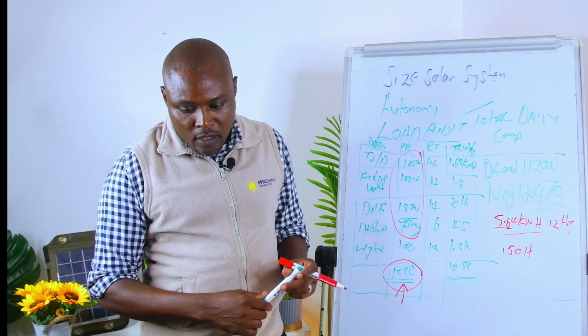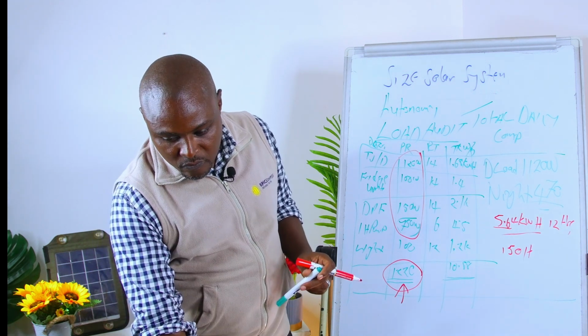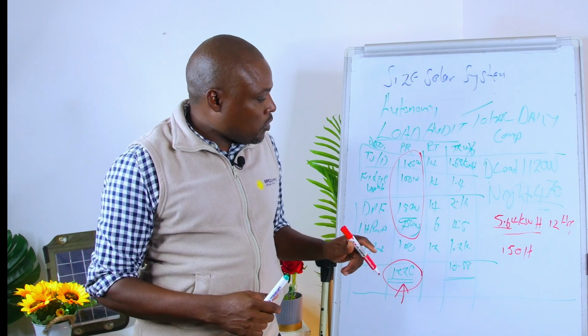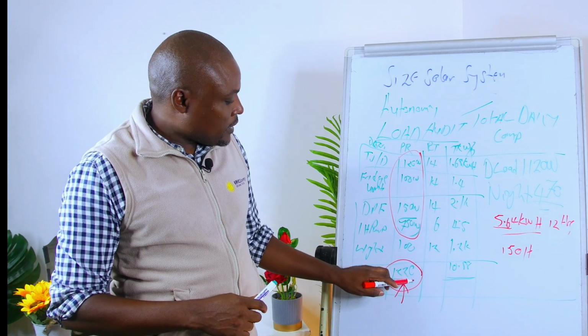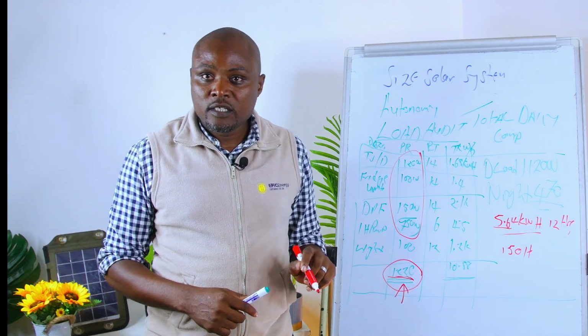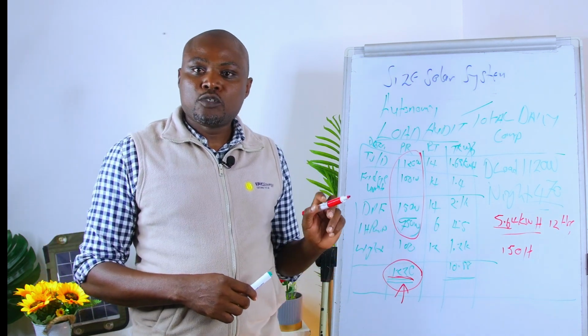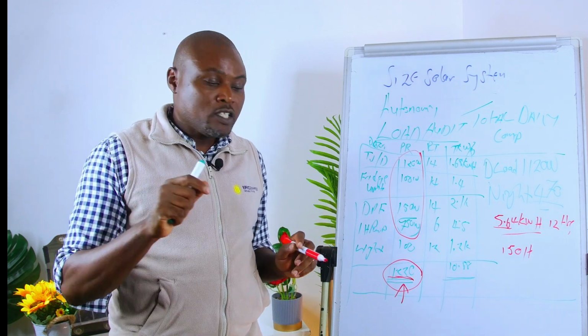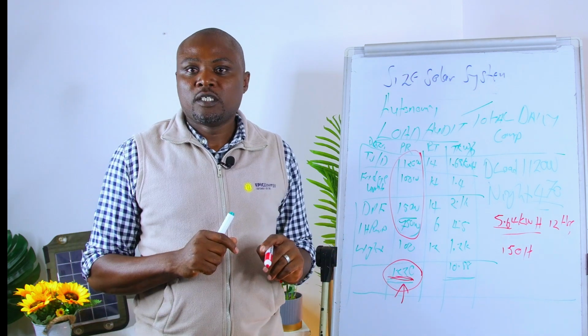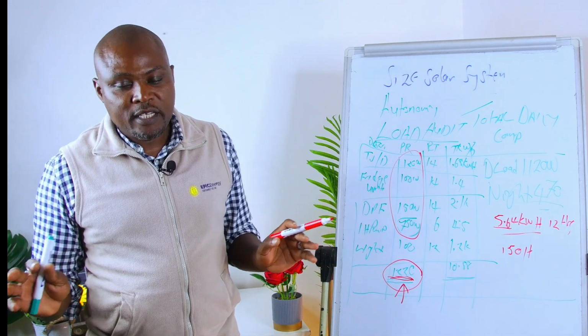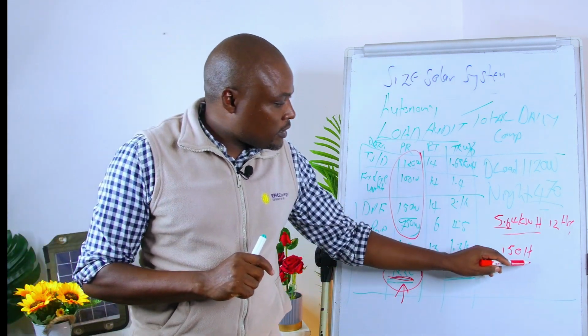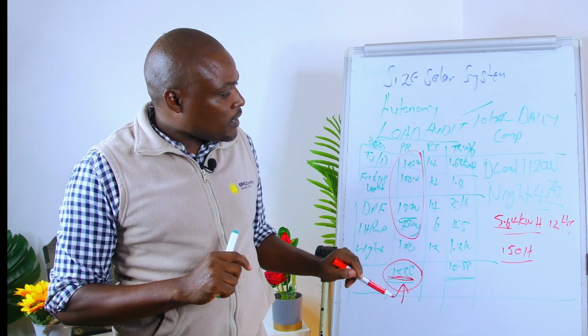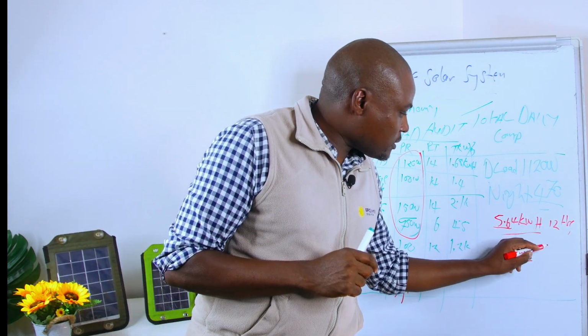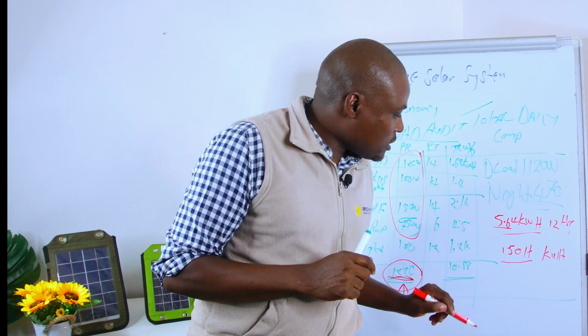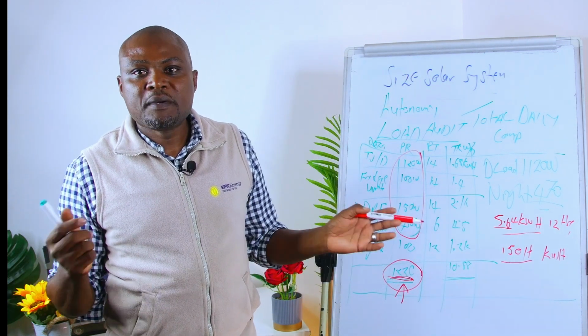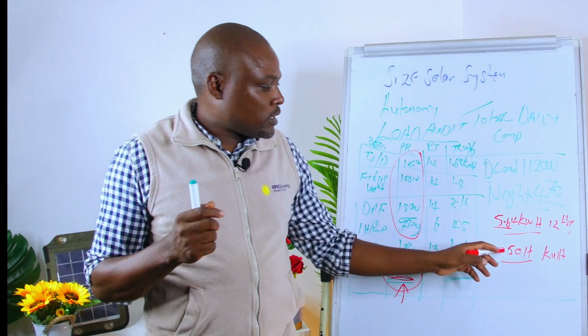So once you know, okay, fine, during the day we want to run this power, you want to run 1,200, but that's not all. You also want to be running, to make sure your battery is being charged during the same time you are powering this load, so that you are not switching equipment on and off in this case. So we then have to calculate our 150 Ah battery. We have to convert it to kilowatt hours, to then find out how many watts you need, maybe over 8 hours, in order to recharge this battery.